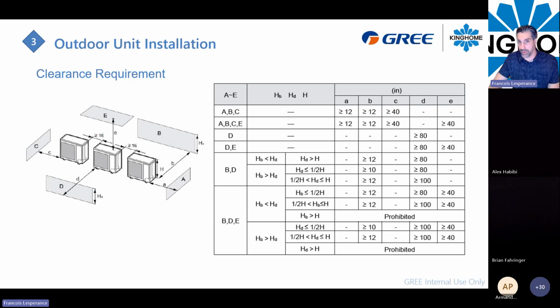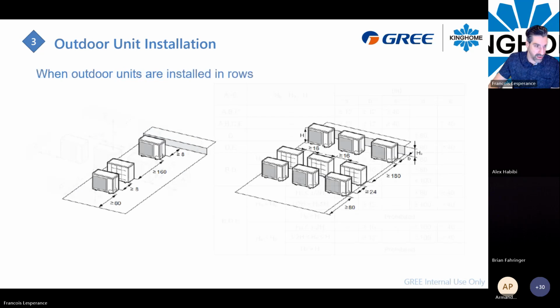Same kind of requirement if you have multiple units installed. So 12 inches in the back. Well, if you have multiple units here, we recommend 16 inches, but the same 40 inches in front of the unit. So you can have multiple units side by side like this, installed in a row. If the units are facing back to back like this, 8 inches is recommended. And if they are facing front to front like this, 160 inches is recommended.